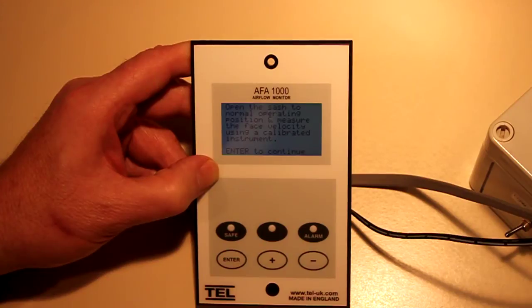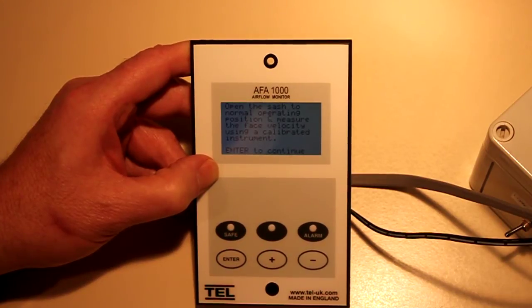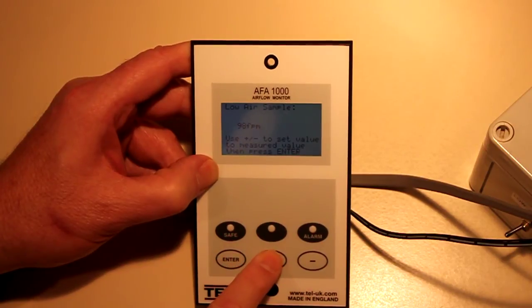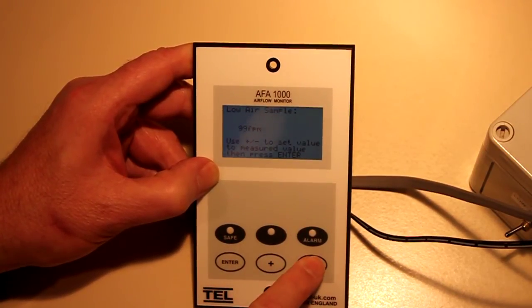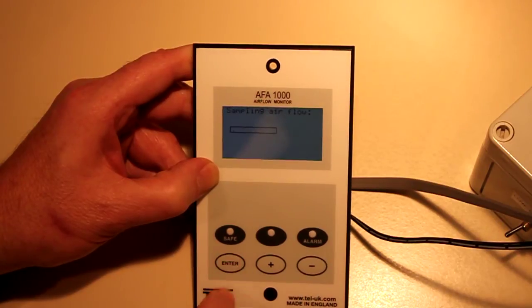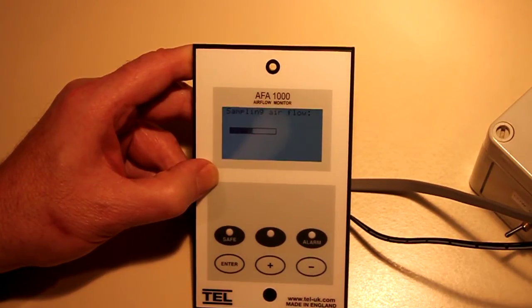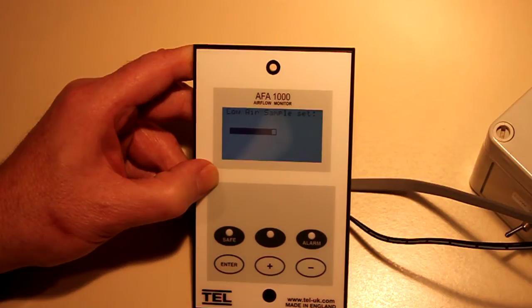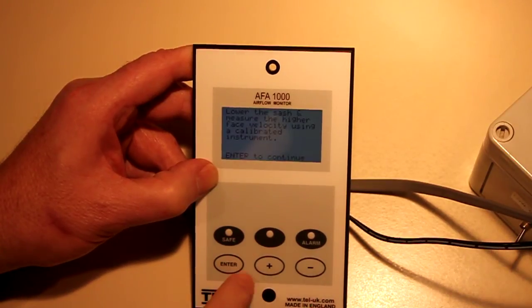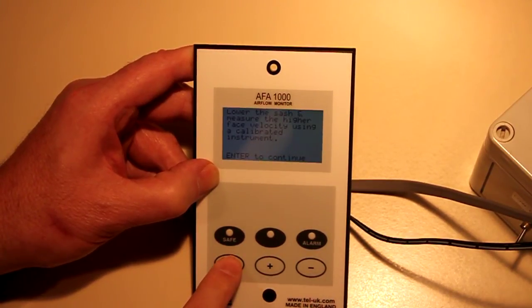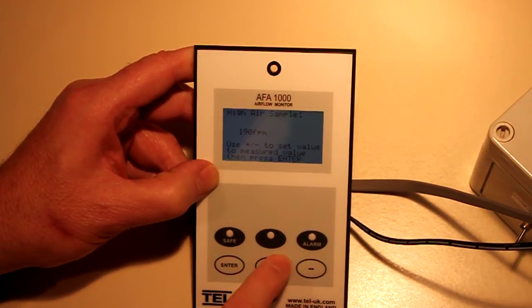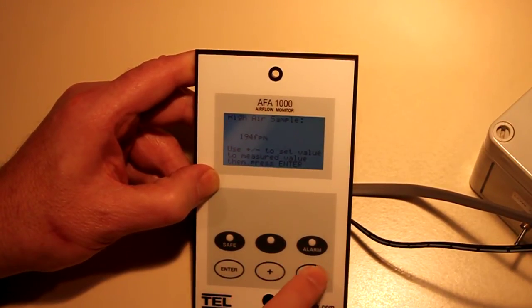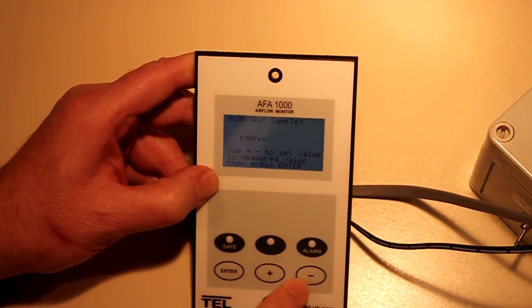This demonstration unit allows us to simulate airflow. In a laboratory setting, you will need to measure fume hood face velocity with a calibrated instrument. Following the instructions on the screen, open the sash to normal operating height, such as 18 inches, and take airflow measurements. Using the plus and minus keys, input the measured velocity and press the Enter button to initiate airflow sampling. After the low air sample is complete, lower the sash halfway, such as to 9 inches. Repeat the airflow measurement process, and again use the plus and minus keys to input the measured velocity, and hit the Enter button to initiate airflow sampling.